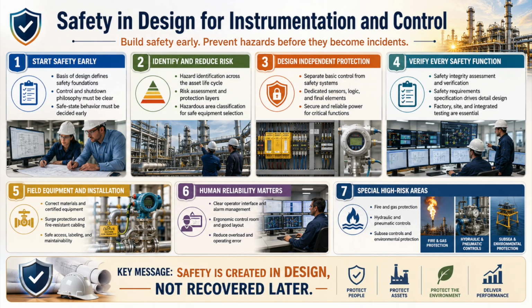Verification asks whether each engineering phase was completed correctly. Validation asks whether the installed system actually performs the required function. Both are essential. A correct calculation cannot rescue a wrongly installed valve. A successful software test cannot prove that an impulse line is clear. A perfect drawing cannot compensate for an untested final element.